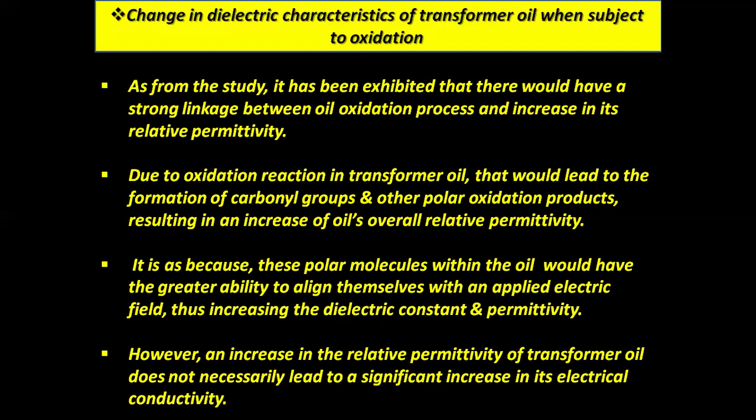It is because these polar molecules within the oil have a greater ability to align themselves with an applied electric field, thus increasing the dielectric constant and permittivity. However, an increase in the relative permittivity of transformer oil does not necessarily lead to a significant increase in its electrical conductivity.